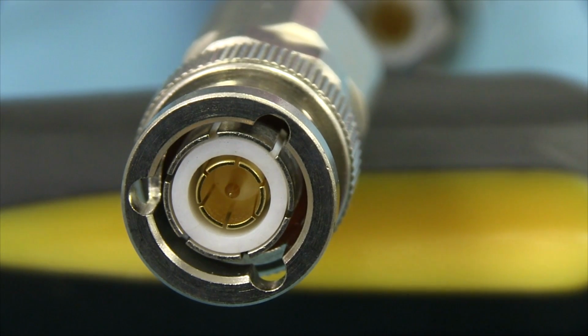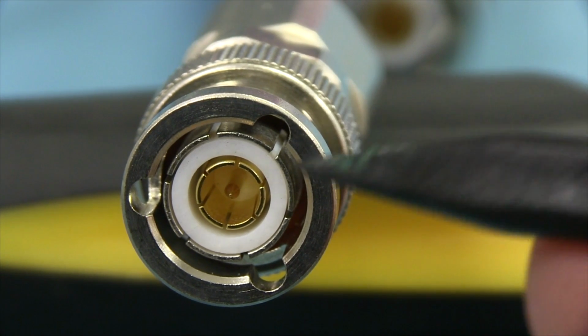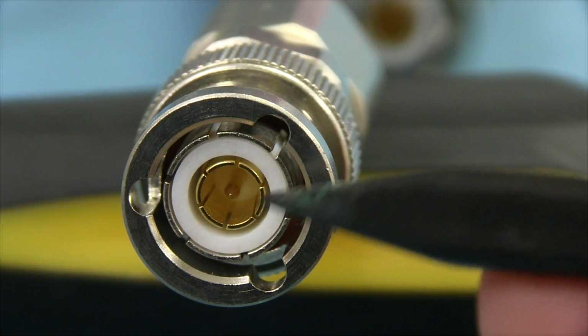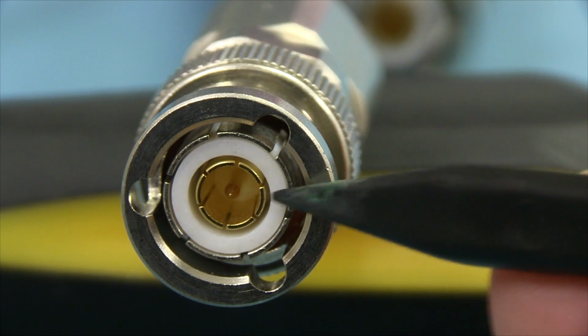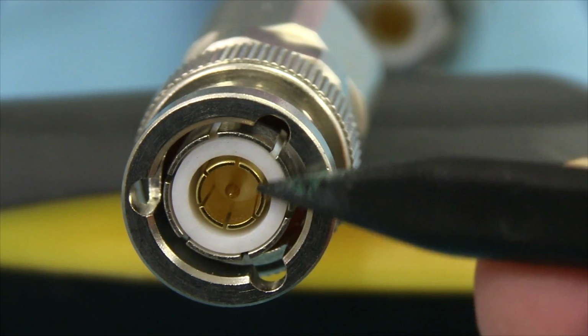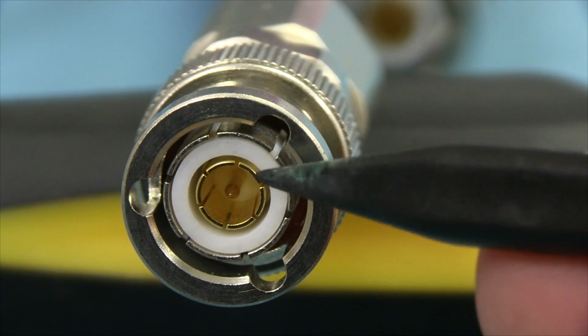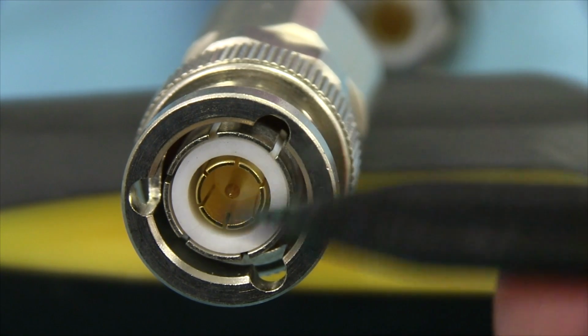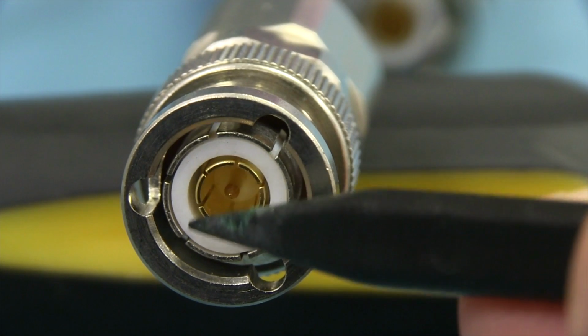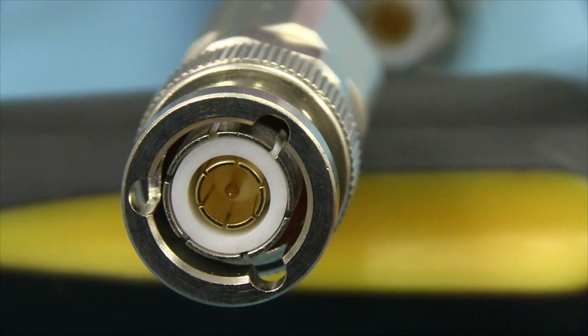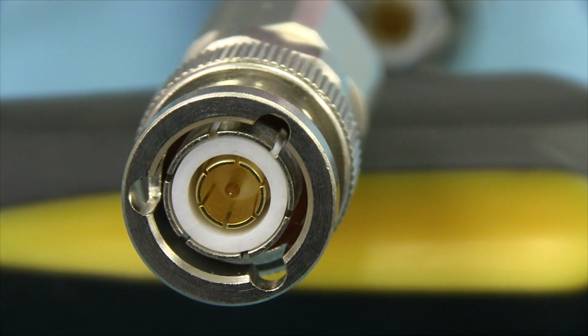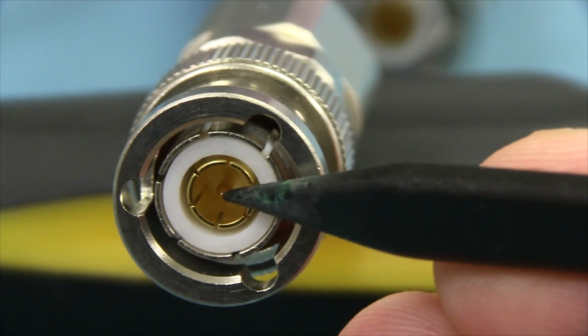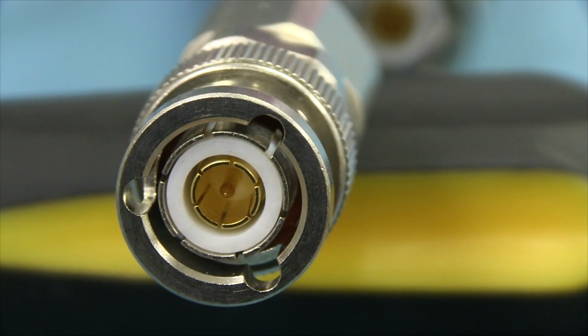So that one keeps out the 50 hertz hum, but that's not good enough for these measurement systems. You also need another secondary shield inside there, so it's physically going to have its own braid inside the coax, and that's connected through to that inner ring there, and that one's connected through to your guard terminal. So that's connected to your measurement system common inside the instrument, and that's very important. And then finally, you've got your test signal in the center conductor.